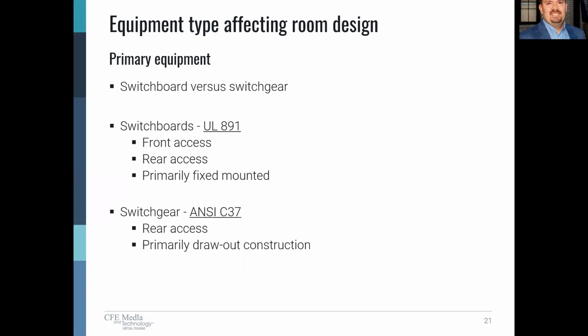In the case of switchgear, they always require rear access in addition to front access. And the overcurrent protective devices in the lineup are draw-out construction. Basically, they can be pulled out like a drawer for maintenance and serviceability. It's important that our working clearances not only accommodate access, but that we take into consideration, in the case of switchgear, the draw-out function of the gear.